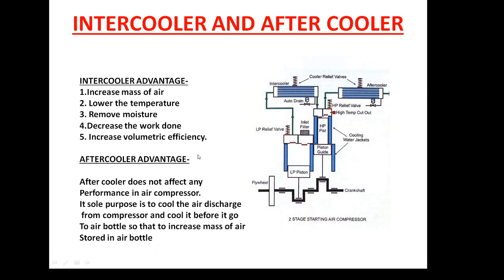Now first let's talk about what an intercooler is. An intercooler is a device which cools the air discharged from the first stage, on its way to the second stage. In between the stages it cools the air in the line connecting the two. Why is it provided? It is provided so that it can remove the heat gained during compression.